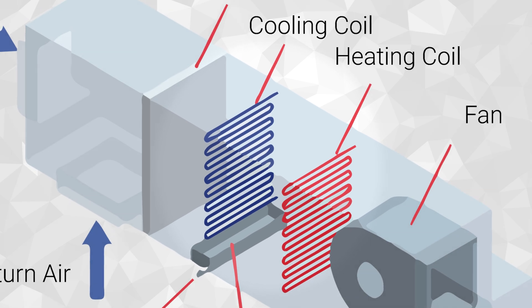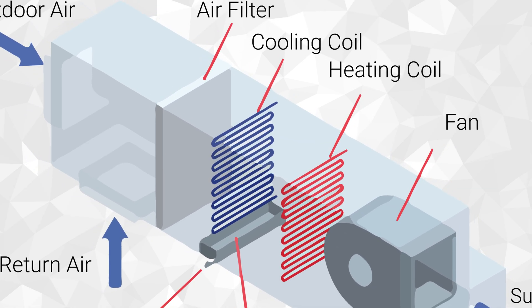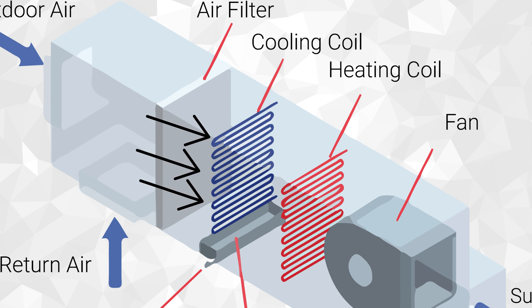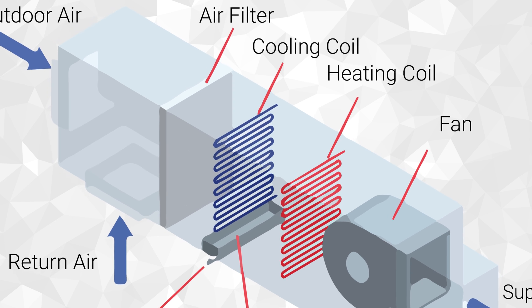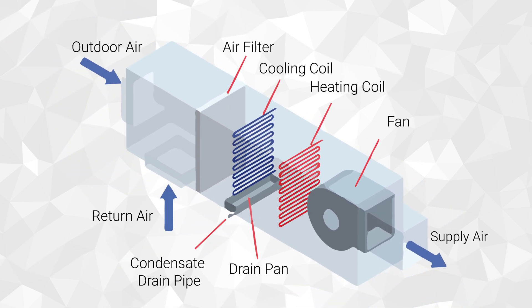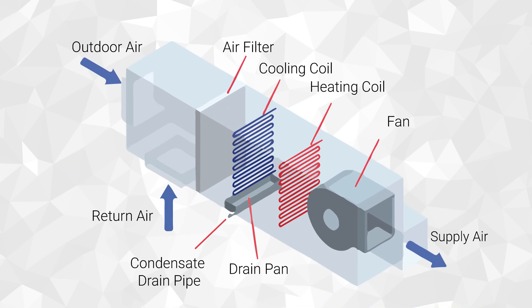For instance, if you're cooling a space, the chilled water is supplied to the coil via pumps and valves. As the air moves through the coil, the coil and water absorb the heat in the air, and the air becomes cooler. Condensation forms on the coil, removing moisture from the air. The fan then blows the newly conditioned air into the duct system, where it moves through the facility as needed.